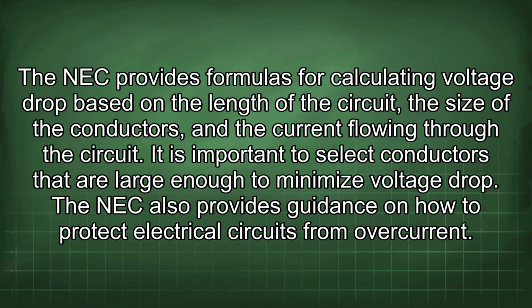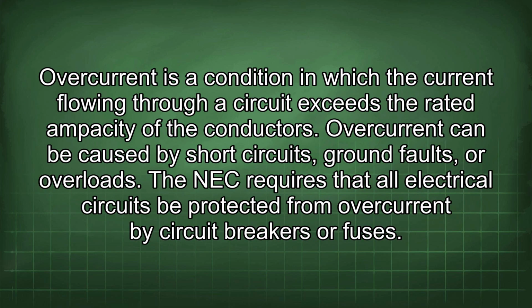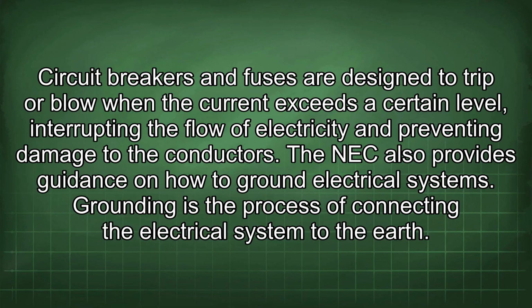The NEC also provides guidance on how to protect electrical circuits from overcurrent. Overcurrent is a condition in which the current flowing through a circuit exceeds the rated ampacity of the conductors. Overcurrent can be caused by short circuits, ground faults, or overloads. The NEC requires that all electrical circuits be protected from overcurrent by circuit breakers or fuses. Circuit breakers and fuses are designed to trip or blow when the current exceeds a certain level, interrupting the flow of electricity and preventing damage to the conductors.